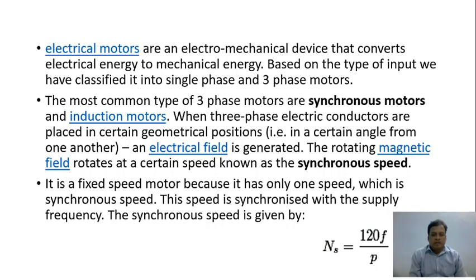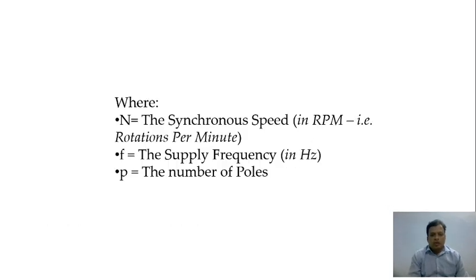So in these three phase motors, the conductors are in certain geometrical positions at an angle from one another, and the field is generated. The rotating magnetic field rotates at a speed known as the synchronous speed. So it is a fixed speed motor because it has only one speed, the synchronous speed. This speed is synchronized with the supply frequency, and the synchronous speed is given by the formula Ns = 120 f / P, where Ns is the synchronous speed in RPM, that is rotations per minute, f is the supply frequency in Hertz, and P is the number of poles.